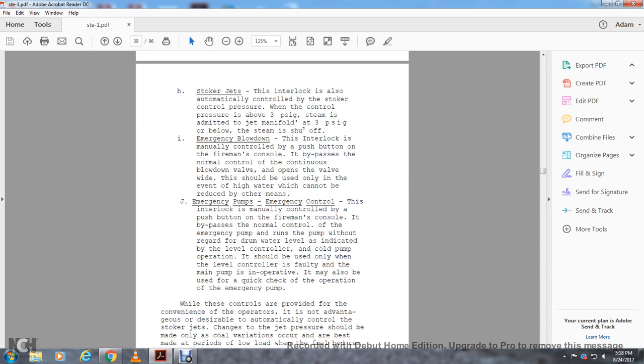Emergency pumps. The emergency control. This interlock is manually controlled by the push button on the fireman's console. It bypasses the normal control, running the emergency pump without regard for the drum water level as indicated by the level controller.